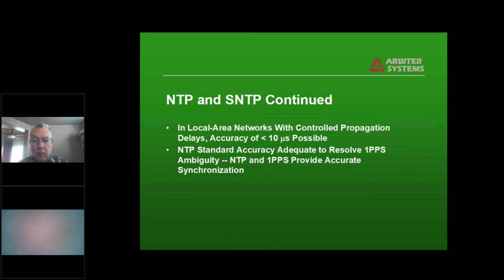In local area networks with controlled propagation, 10 microseconds is feasible, but that requires very good care in the design of the sending and receiving equipment. SNTP and NTP almost always operate on an interrupt basis, so you have to have the interrupt generate a time tag as soon as possible after the message is received, and calibrate out sources of error.